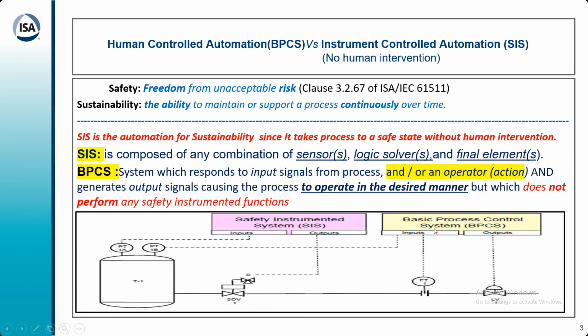BPCS do fail, and most of the major accidents which have occurred, occurred because there was no separate SIS. In this diagram, the standard says you should go for a separate safety instrumented system. A separate system means a separate transmitter at the input, and a separate output to the final control element, and here the final control element is a solenoid operated on-off valve. It is not a regulatory valve. So this is independent of BPCS. This system will work independently. That means if this SIS fails, your BPCS can still continue to work.